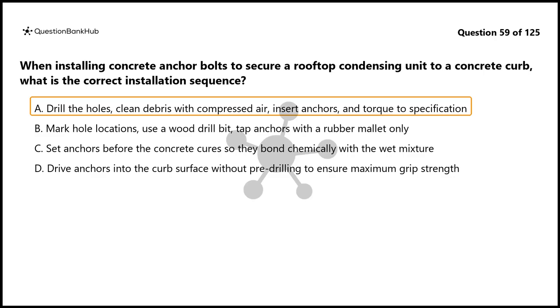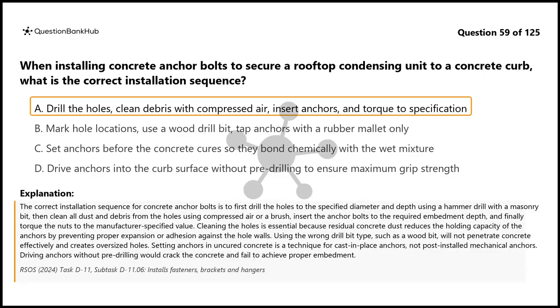The correct answer is A. The correct installation sequence for concrete anchor bolts is to first drill the holes to the specified diameter and depth using a hammer drill with a masonry bit, then clean all dust and debris from the holes using compressed air or a brush, insert the anchor bolts to the required embedment depth, and finally torque the nuts to the manufacturer specified value. Cleaning the holes is essential because residual concrete dust reduces the holding capacity of the anchors by preventing proper expansion or adhesion against the hole walls.